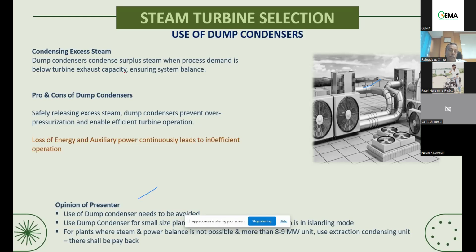So using a dump condenser, point number one, it is a capital cost, though not a big one, but it is a continuous loss of power. When you are dumping, you are losing energy continuously. In some plants, because of the particular plant configuration, we are not at all able to balance between power and steam. In that case, we don't have any option but to go for a dump condenser.